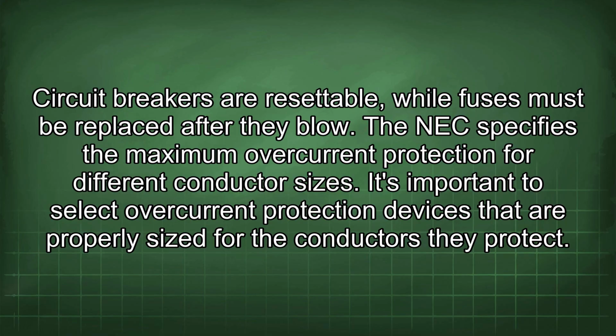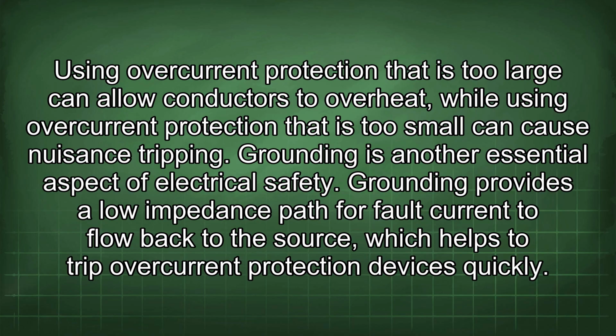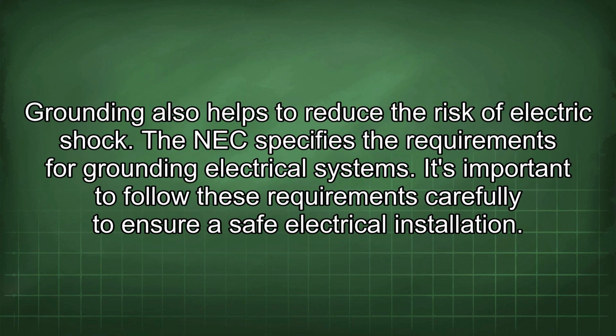The NEC specifies the maximum overcurrent protection for different conductor sizes. It's important to select overcurrent protection devices that are properly sized for the conductors they protect. Using overcurrent protection that is too large can allow conductors to overheat, while using overcurrent protection that is too small can cause nuisance tripping. Grounding is another essential aspect of electrical safety. Grounding provides a low impedance path for fault current to flow back to the source, which helps to trip overcurrent protection devices quickly. Grounding also helps to reduce the risk of electric shock.